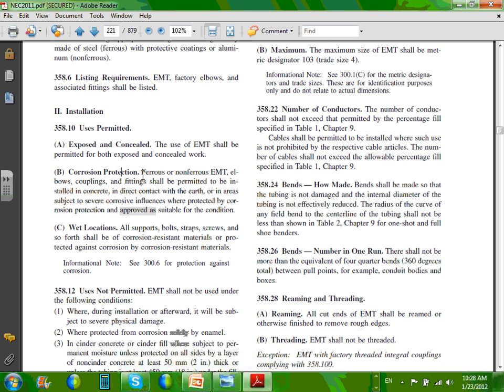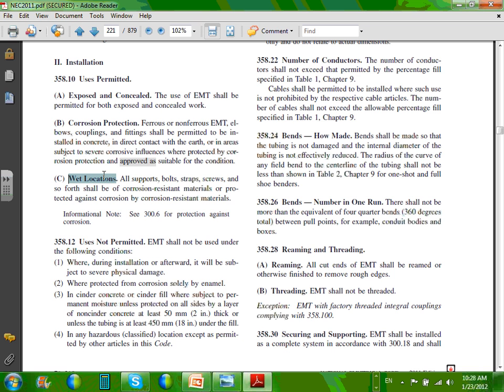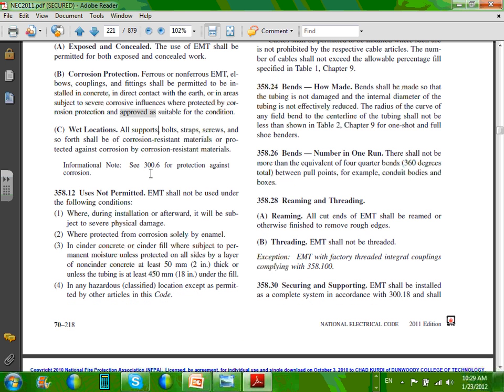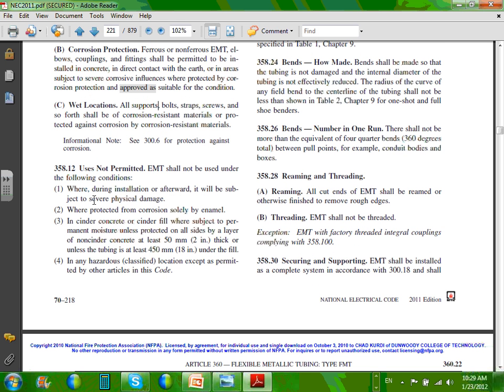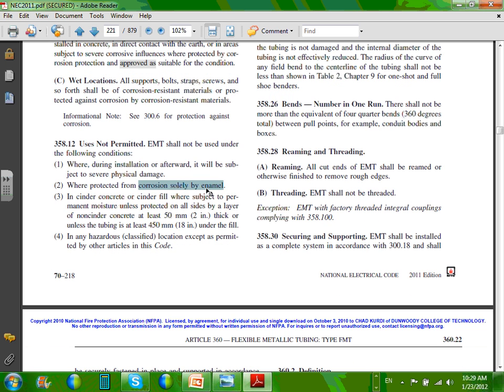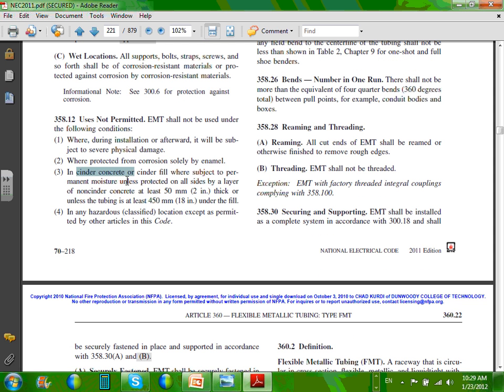Corrosion protection, you have to have some type of protection if it's in corrosion areas. Wet location, can I use it in a wet location? All supports, bolts, blah, blah, blah. You can use it in a wet location, but it shall be corrosion resistant. Any wet location, guys, is exposed to corrosion. You have to be very careful, though, it's not really a wet location conduit, but you can use it outdoors, above ground, in a wet location. Uses not permitted: where subject to severe physical damage, you can't use that baby. Corrosion, solely where we have some corrosion protection only, this type. In concrete and cinder, so it's all about corrosion here.